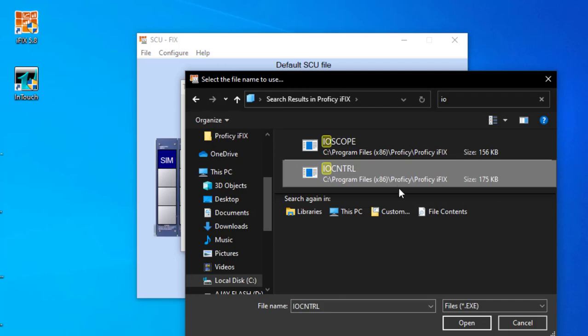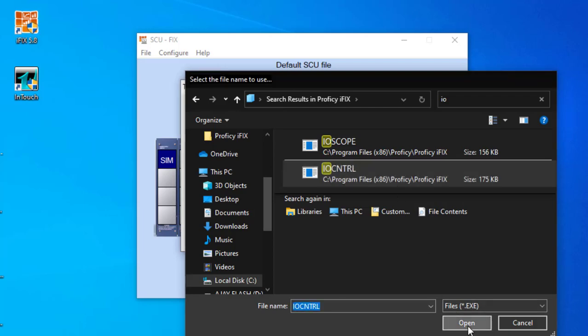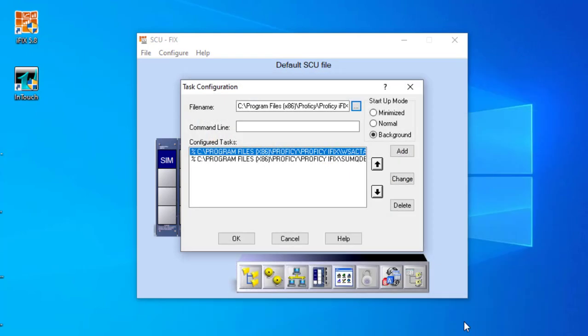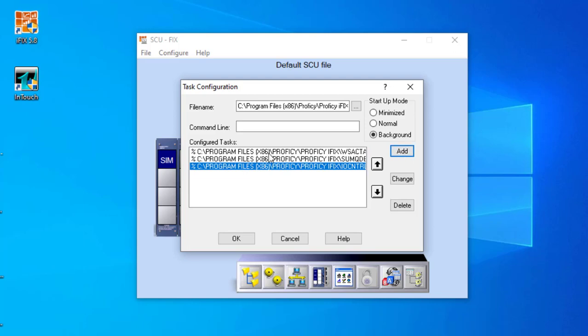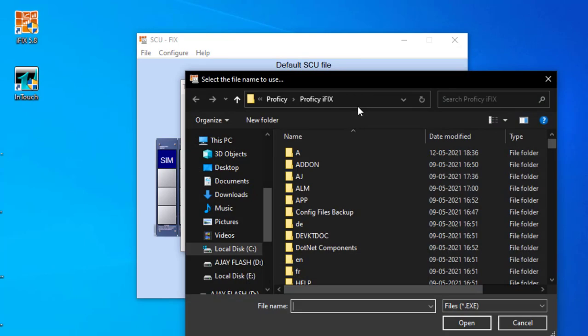I have to search for IO — that will give us the IO Control. The IO Control is important: only when the IO Control is on will the SCADA operate functions like historical trends and the OPC server. I select IO Control and add it, so I just add my IO Control.